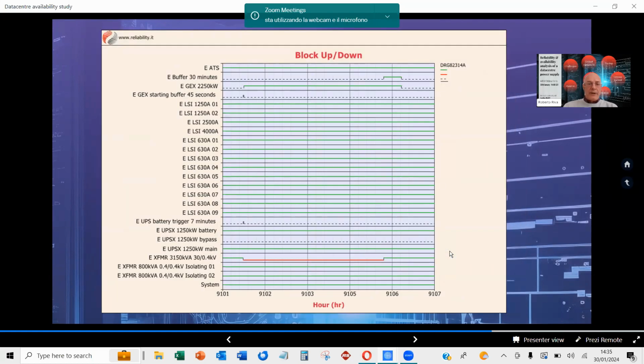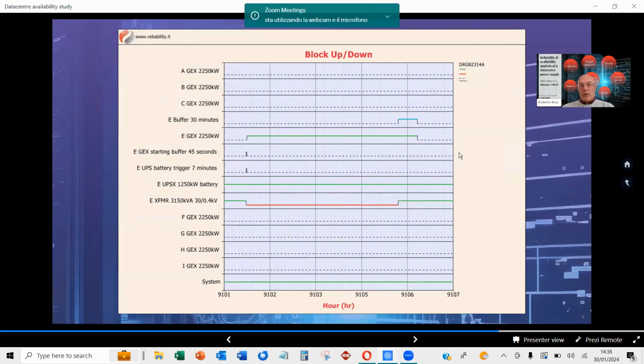And here we got another scenario. We got an E transformer out of use. We got again a trigger, and the E generator comes on, and the buffer time ensures that the generator stays on for another 30 minutes. Obviously, this is, for example, some of the equipment in the E branch. Obviously, we couldn't show it all. If you imagine you've got 470 plus blocks, you can't represent 470 blocks on here. In particular, if you're analyzing a window of 5 years, there's an awful lot of data. So there's a lot of searching and trying to see what's happening because the system is just so congested. Okay, and here there's another one, more or less the same.